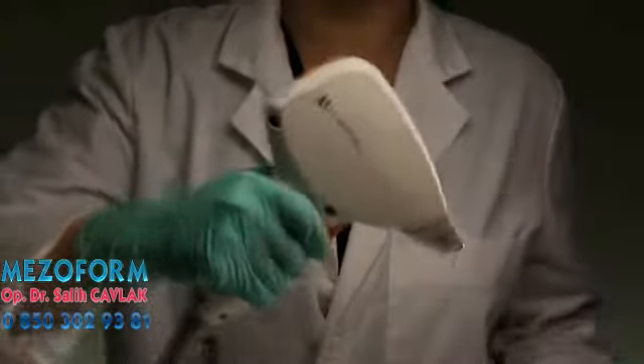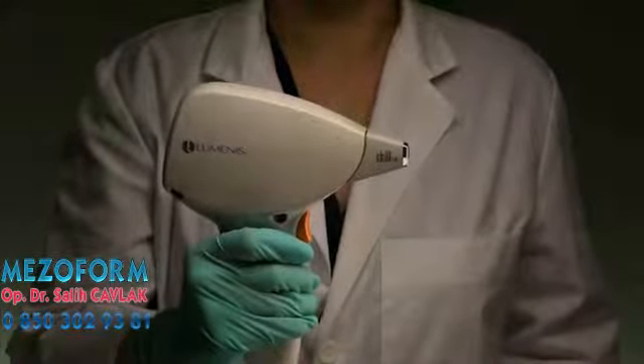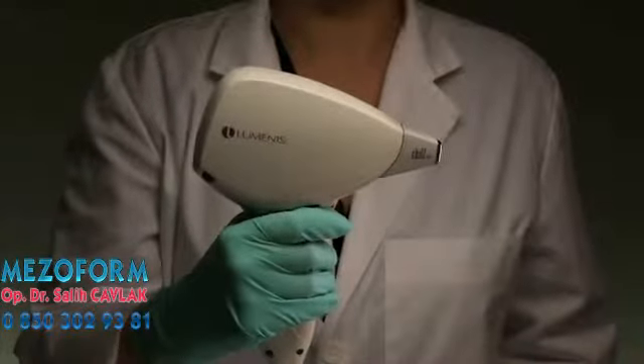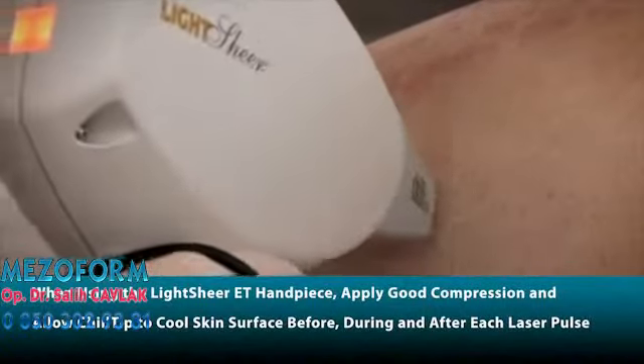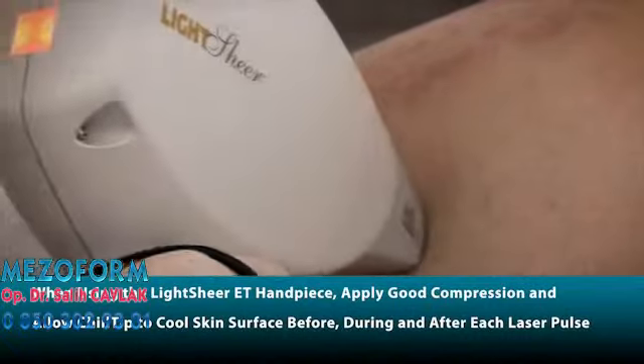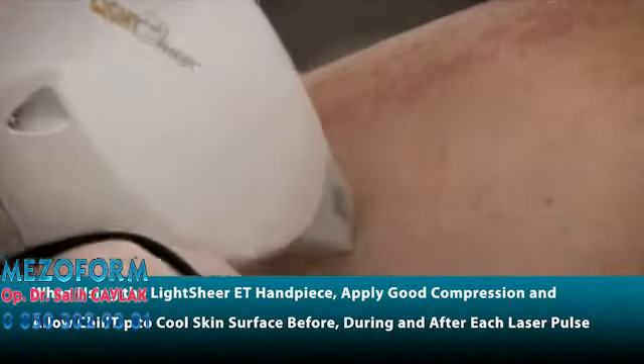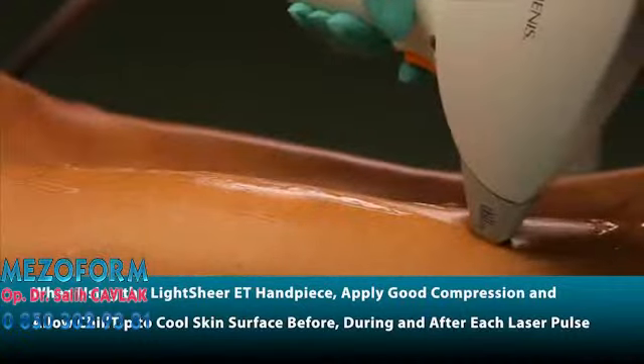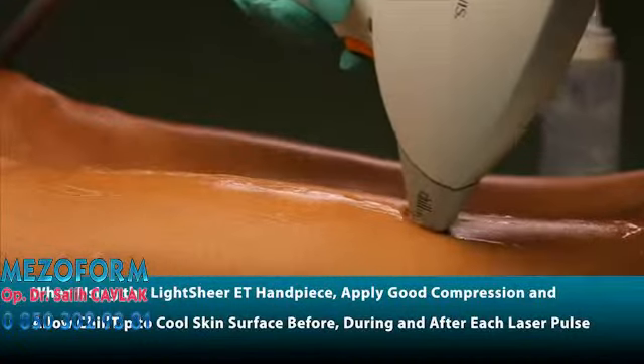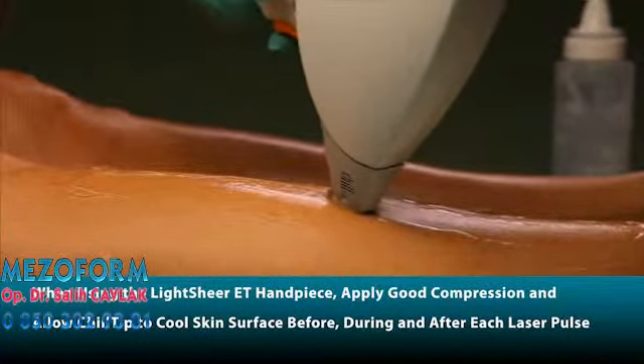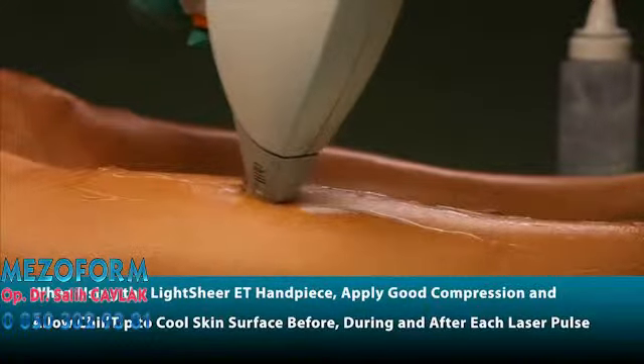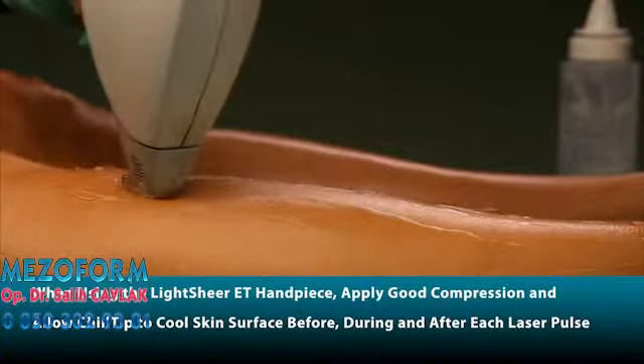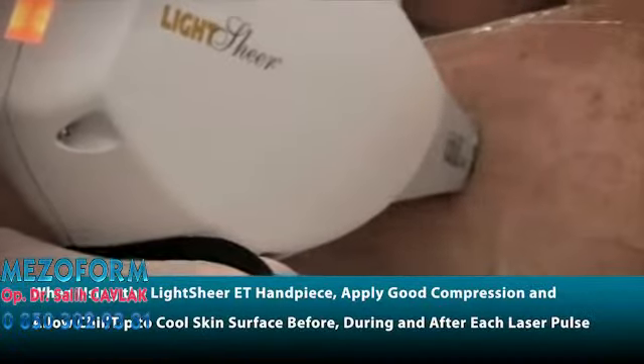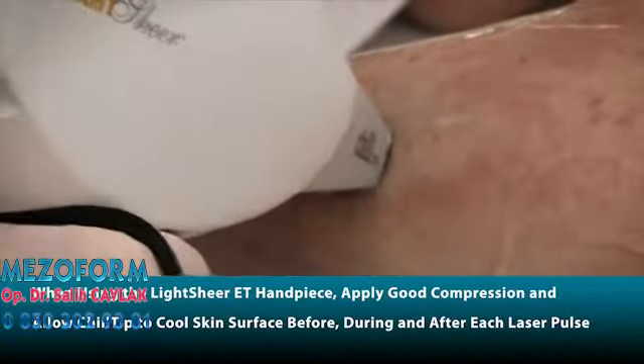To begin the laser treatment, press the handpiece Enable button. This will enable the trigger to be depressed to fire the laser. Pressing and releasing the trigger will result in a single pulse being fired. The laser may be operated in a repetitively pulsed mode by continuously holding down the handpiece trigger. Moderate pressure should be applied to have good contact while using a bounce and glide movement along the skin surface. Do not remove laser tip from the skin surface when using this technique.